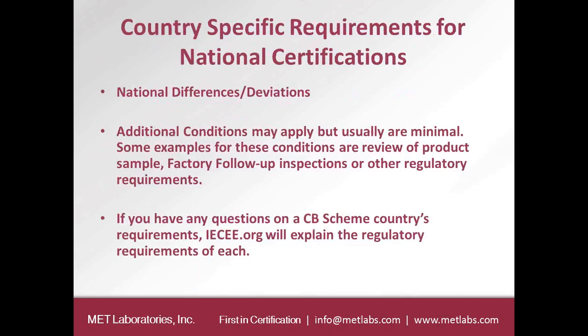As we discussed a little bit, the national differences, special conditions, and regulatory requirements are provided to the IEC and published on their website. The national differences from the IEC standard make up essentially the national standard. As I said, IEC standard is the base standard, and then UL CSA is a local domestic standard which builds upon the requirements of 6950.